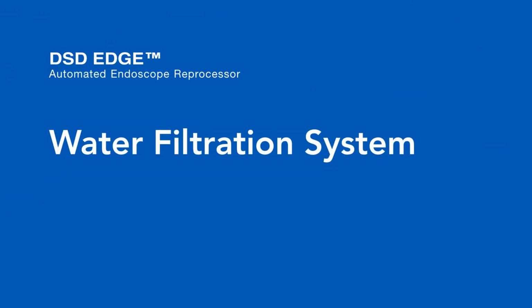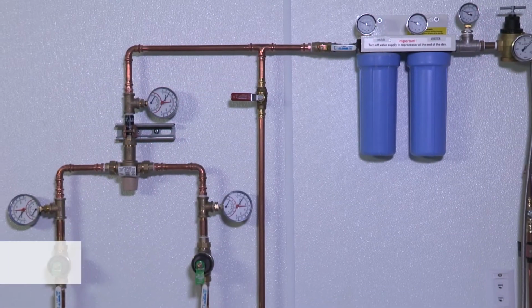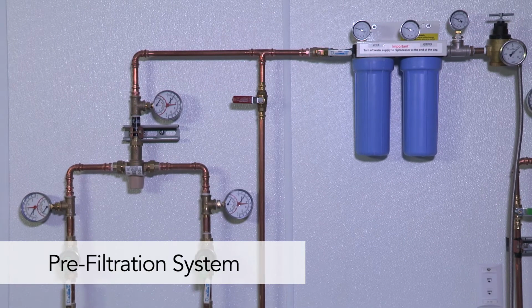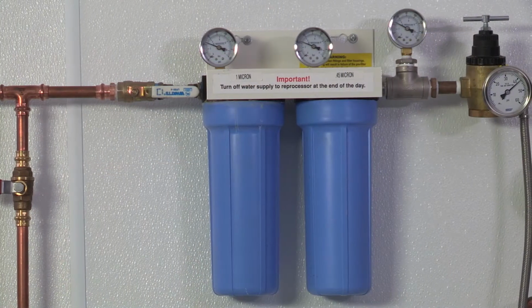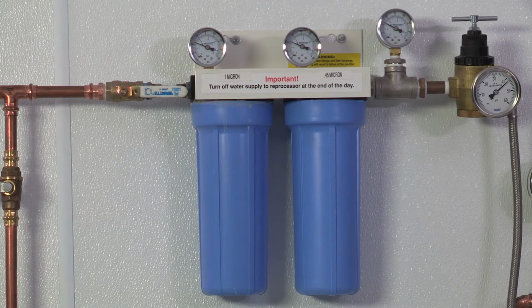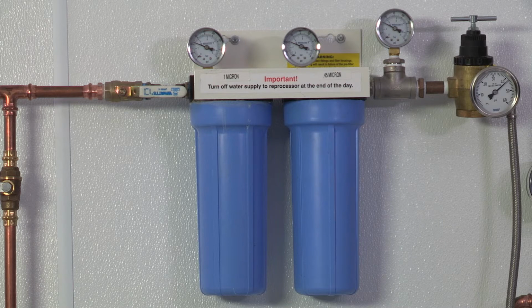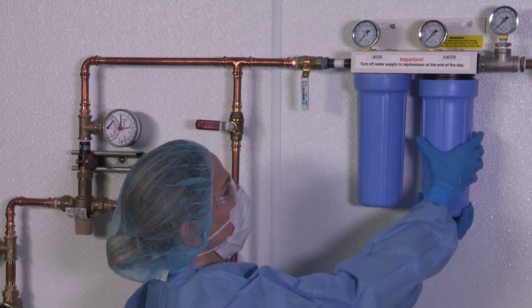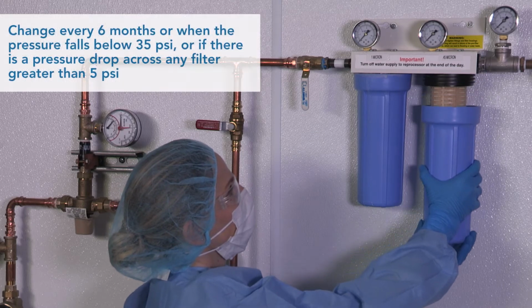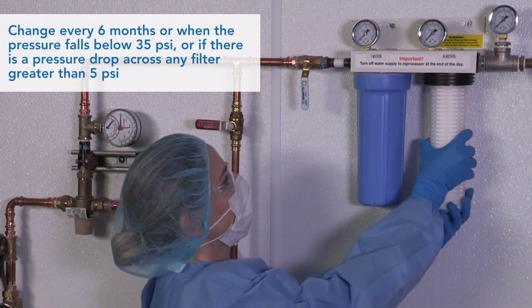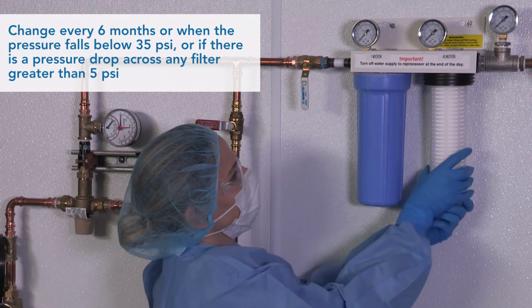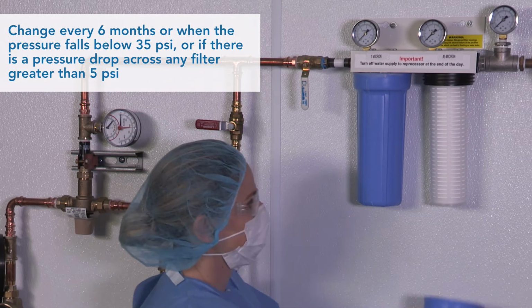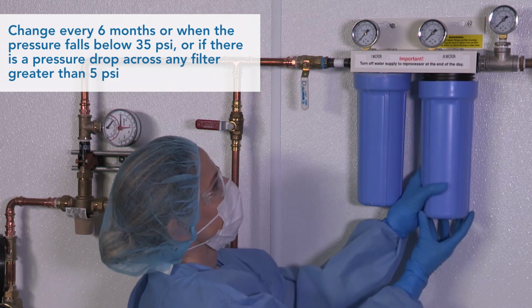The DSD EDGE Reprocessor uses an external wall-mounted dual water pre-filtration system and an internal bacteria retentive filter to provide high-quality rinse water. The pre-filtration system removes particles from the incoming water line in step-down fashion from 1.0 to 0.45 microns. Filters should be mounted where they are easily accessible for the staff and not near electrical outlets. These filters should be changed every 6 months or when the pressure, indicated by the gauges, falls below 35 psi or if there is a pressure drop across any filter greater than 5 psi.